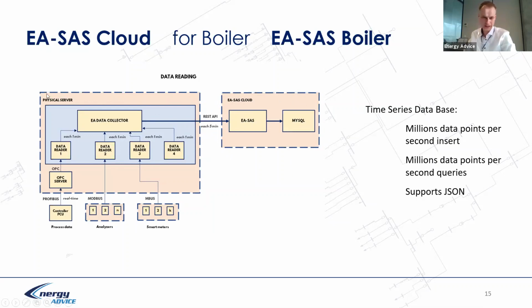However, we put on your client side, on your physical server, data collector software, which collects data, for example, from your PCU controller, for example Siemens, Wonderware, InTouch, or whatever controllers or SCADA system you have inside. We can collect data directly from the controllers, or if your SCADA or control system already has a database, or if you have analyzers or any smart meters, we collect that data also. And if your data is already in a cloud, we can use a REST API to take the data from your cloud and provide the digital twin solution for the biomass boiler. So that is the general structure, what is available, and how we perform.